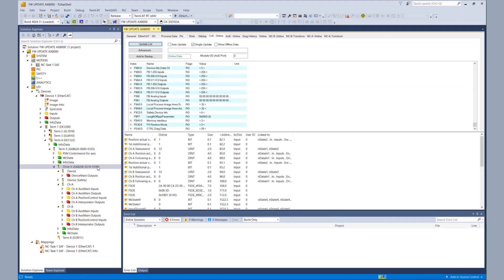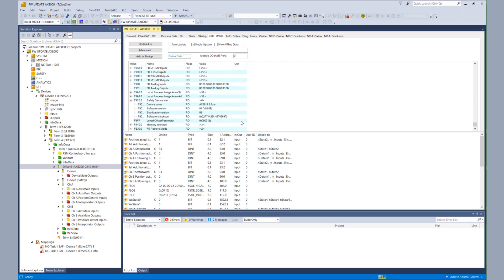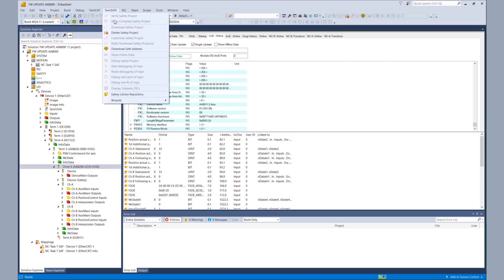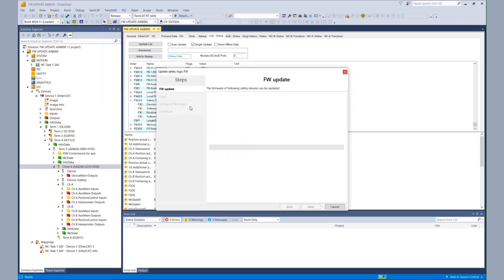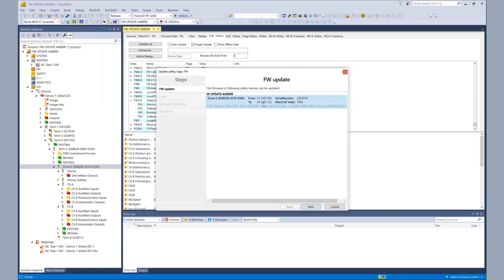So now it's time already to get on with our live demonstration. As I told you before, we have an existing TwinCAT 3 configuration with an AX8000. When we look at the COE object F9C0, we see that currently we have a software version 01 and a bootloader version 09. And then we go over to TwinSAFE Wizards, Start Firmware Update Wizard to get on with our firmware update. We see our connected drive. We want to update from 01 to 03.